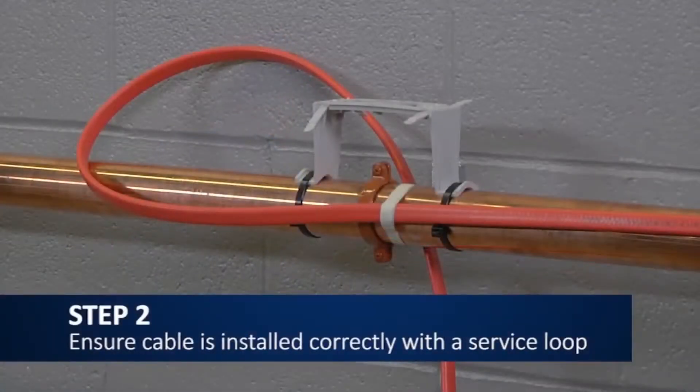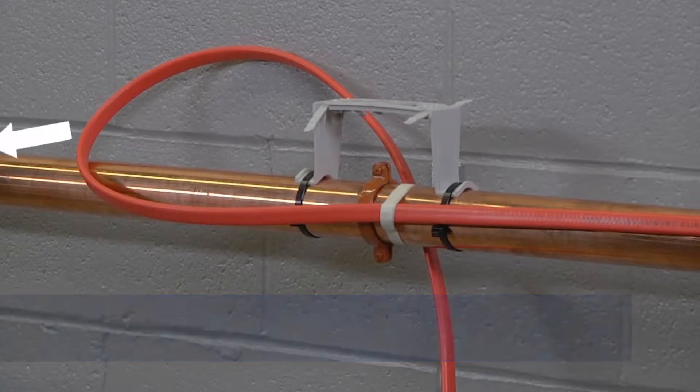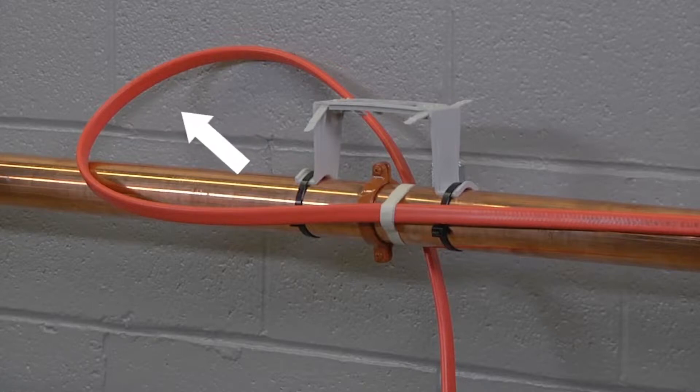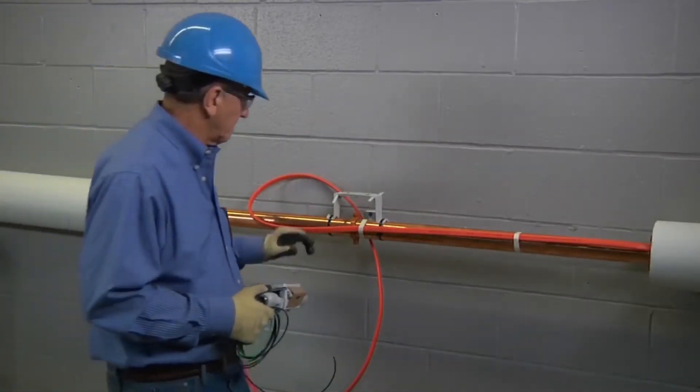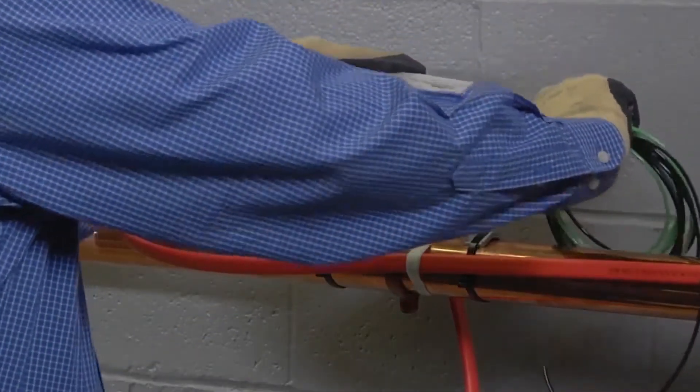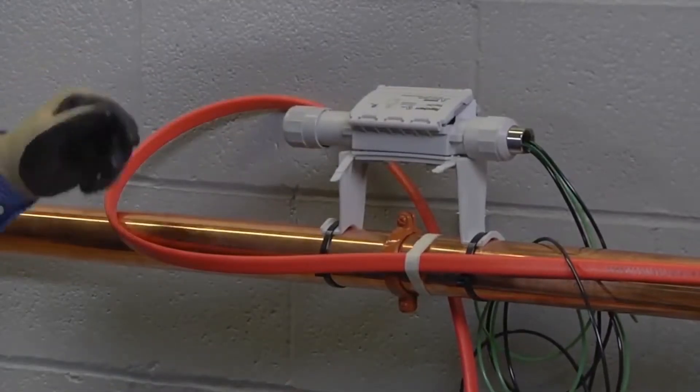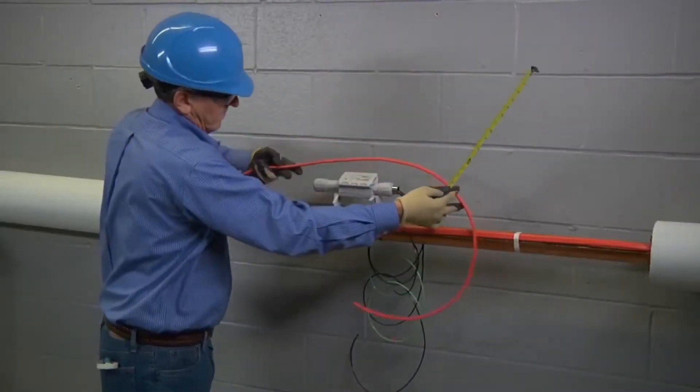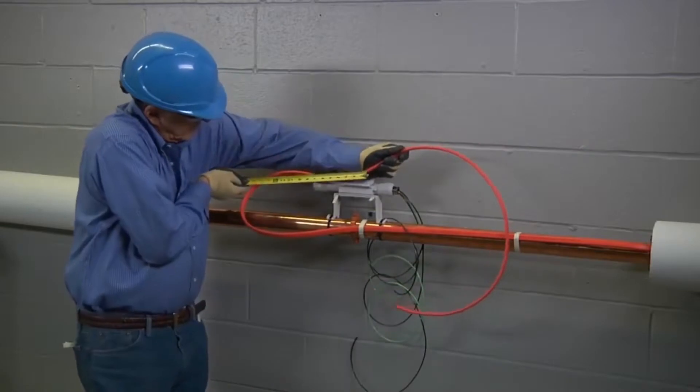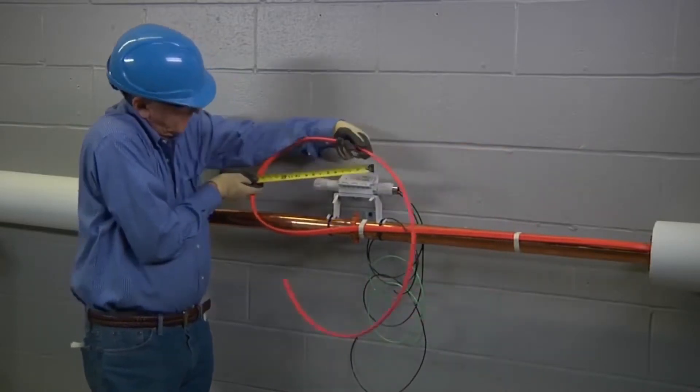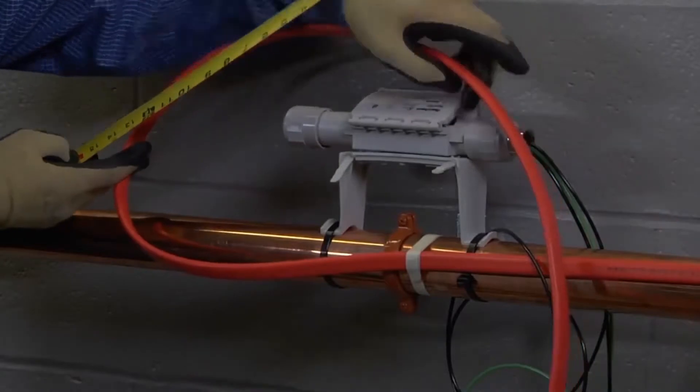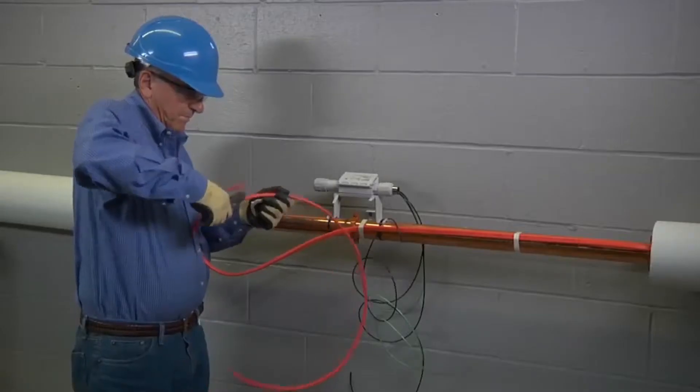Now, ensure that the heating cable - HWatt, XL Trace, RaySol, or Ice Stop - is installed properly on the pipe, and that there is a service loop at the location where the RayClic will be installed. A service loop is done by orienting the RayClic PC on the pipe with the conduit fitting facing towards the electrical junction box, and bending the heating cable 180 degrees, looping back towards the other end of the RayClic PC, allowing at least 12 inches of heating cable slack in order to make the connection.